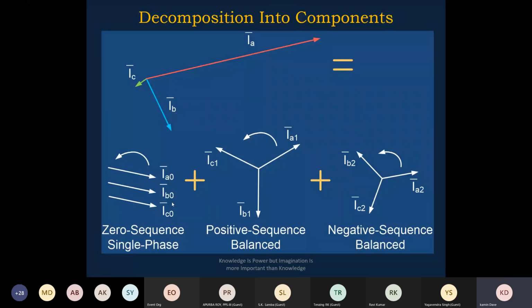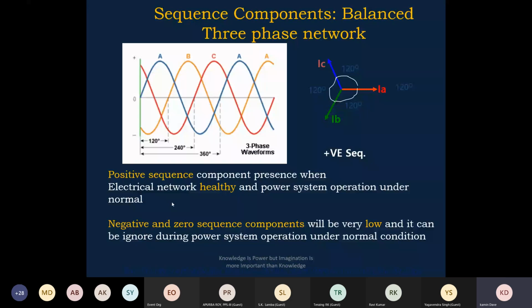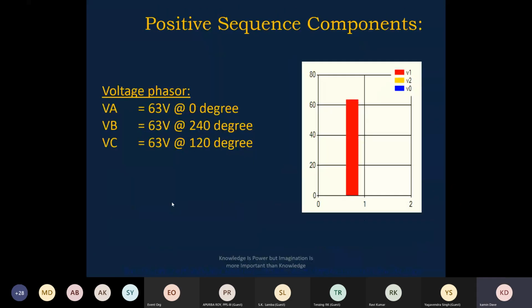Okay, so if you look at it here, this is the positive sequence component, for a balanced power system condition. You see the A phase, B phase and C phase current. A phase current at 0 degree, B phase at 240 degree, C phase at 120 degree. That you look at it here. Now if you look at the symmetrical component phasors, 63 volt at 0 degree, 63 volt at 240 degree, 63 volt at 120 degree. So V1, V2, V0.